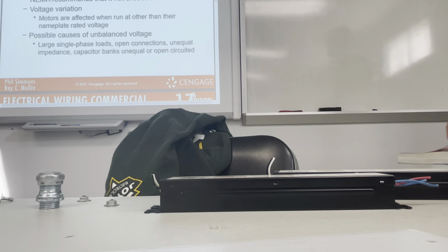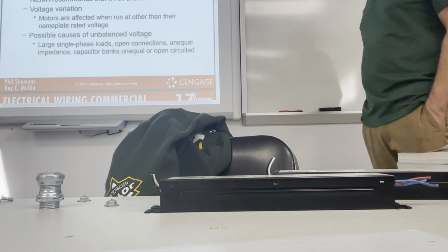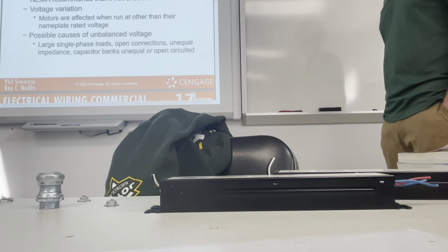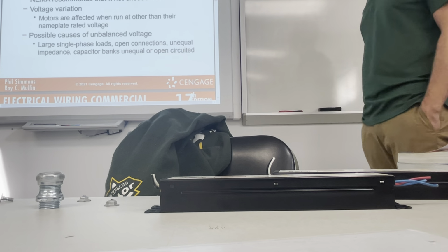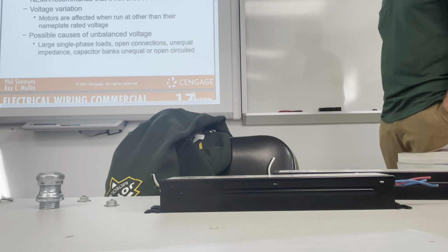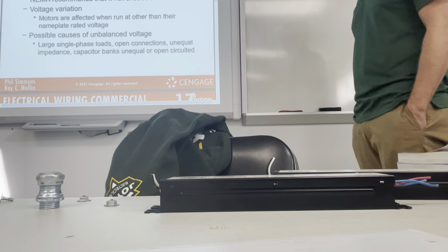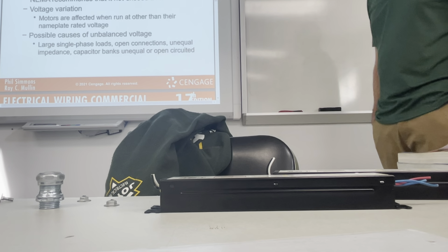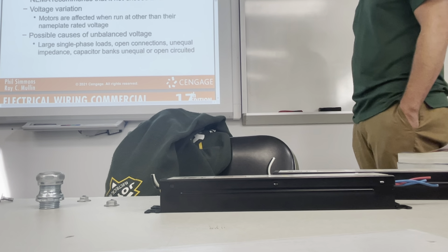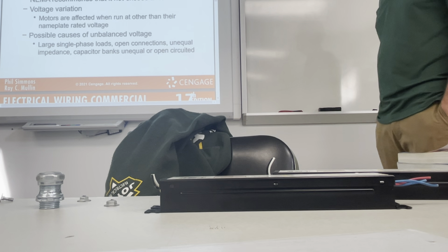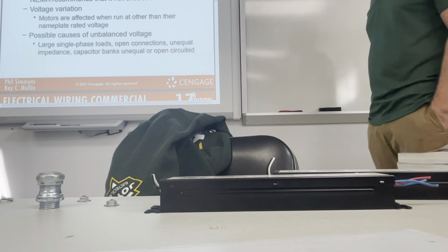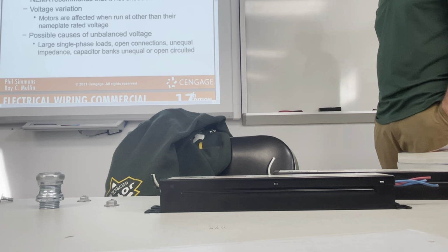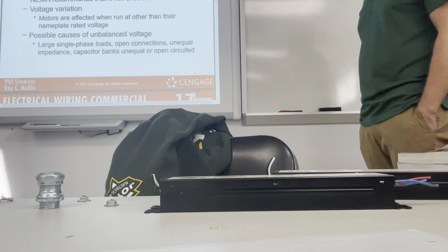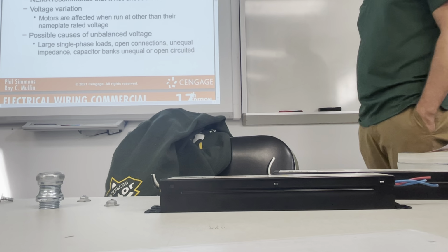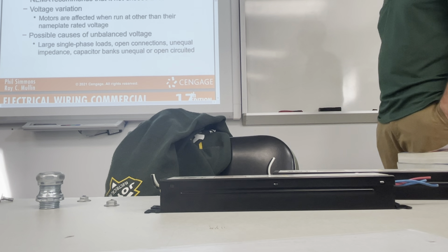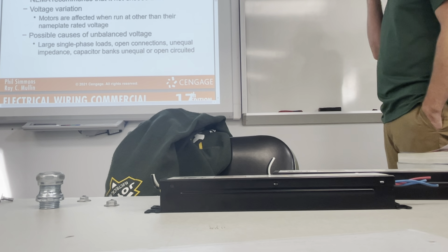Basics of motor circuits. Unbalanced voltage causes unbalanced currents in motor stator windings. NEMA recommends that it not exceed plus or minus 1%. Voltage variation: motors are affected when run at other than their nameplate rated voltage. Possible causes of unbalanced voltage: large single-phase loads, open connections, unequal impedance, capacitor banks, unequal or open circuits.